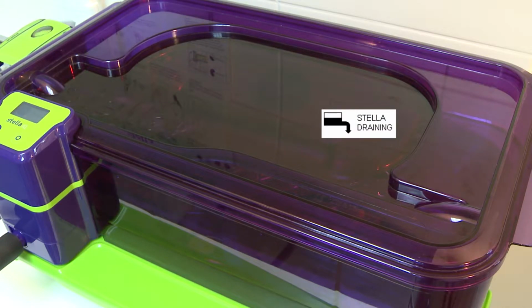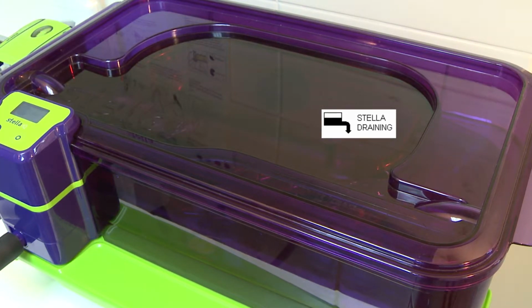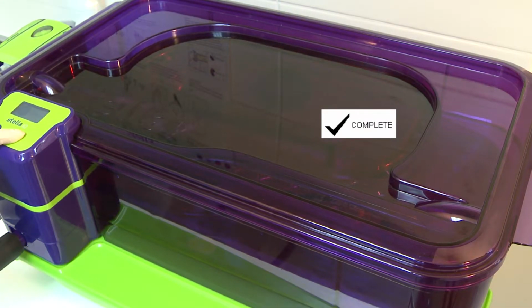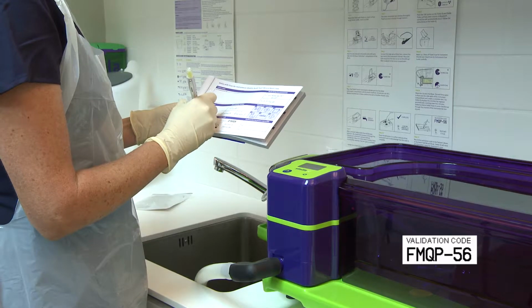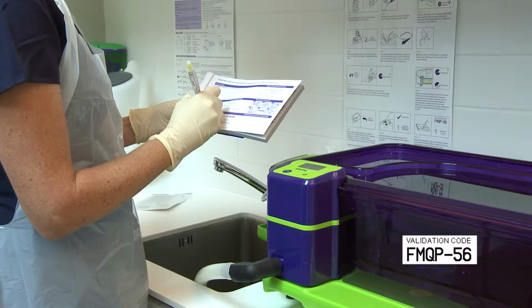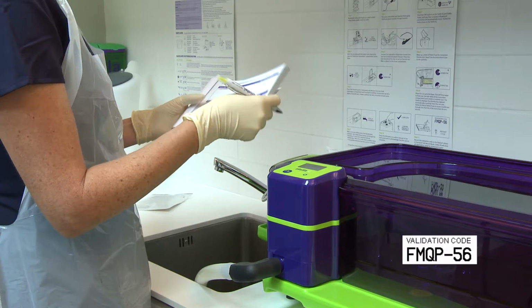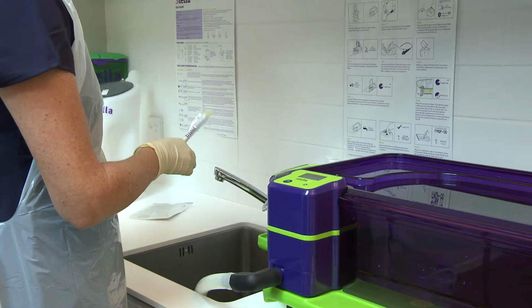After 5 minutes, Stella drains automatically to waste. Stella Pulse pumps to remove residual disinfectant. When the Stella base is empty, there is an audible reminder that the cycle is complete. Press the OK button to confirm removal of the instrument and that the cycle is complete. Record the validation code that is shown on the IQ LCD screen in the audit trail record book.